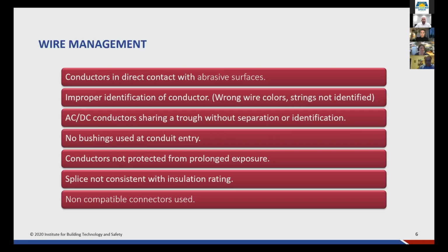Where we see this fail, and some of the bigger issues, are where conductors are in direct contact with abrasive surfaces. Maybe we're misidentifying the conductor by using the improper colored wire insulation, or otherwise not keeping that consistent throughout the system. Oftentimes we'll see AC and DC conductors sharing a trough in commercial situations, maybe being installed on some farm or some pre-existing tie-in effort, where final home runs get laid into a shared trough, which is absolutely not allowed.